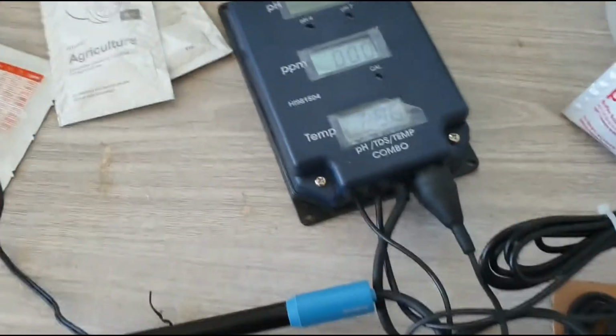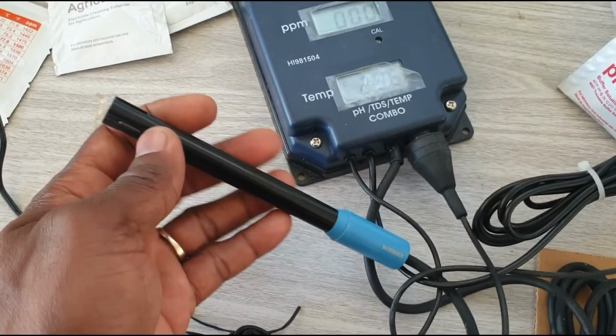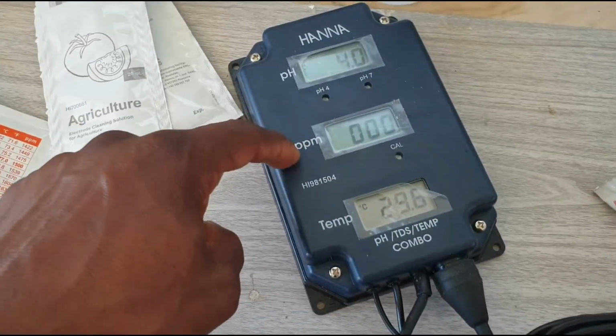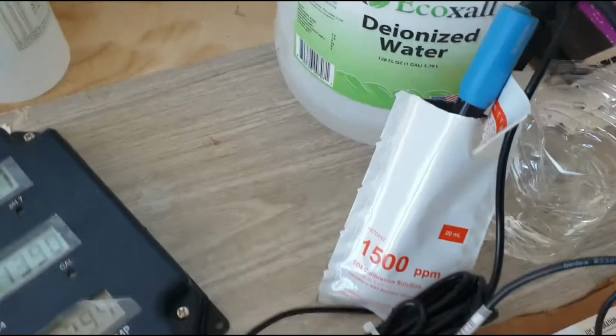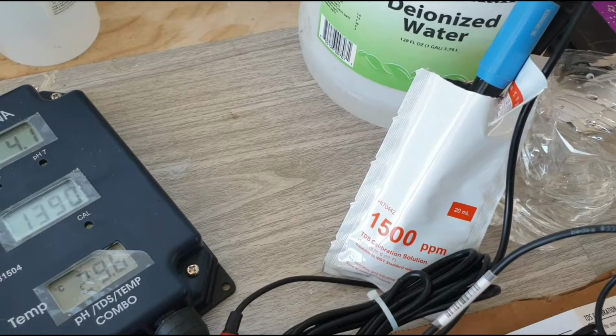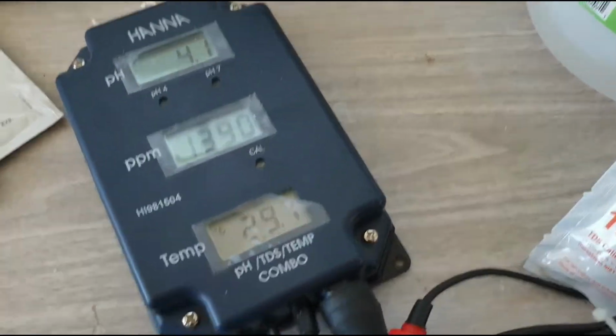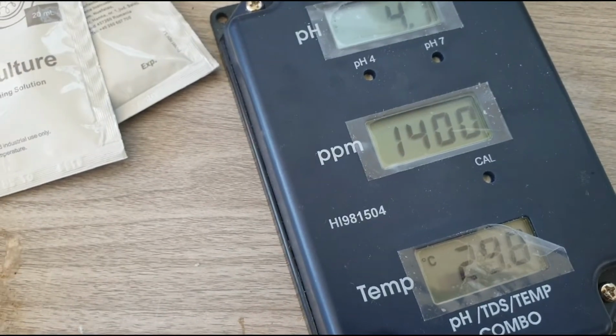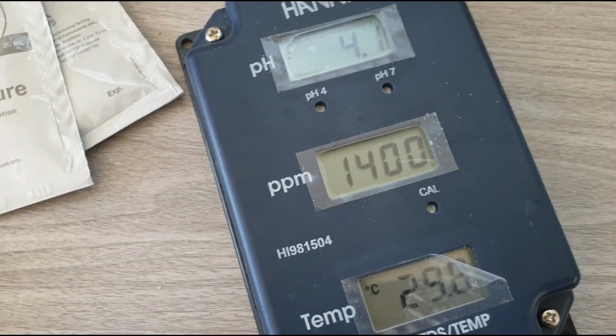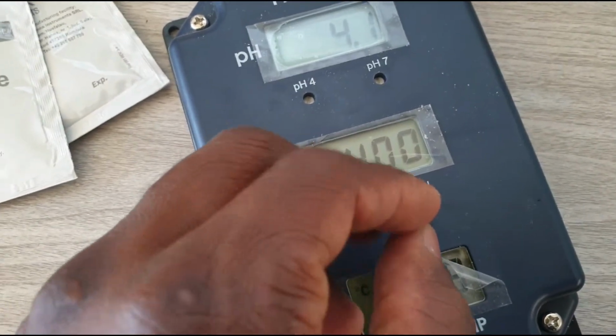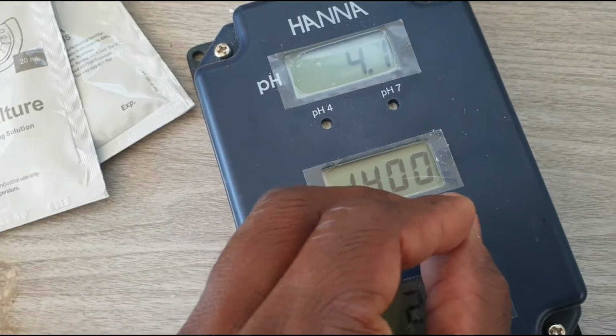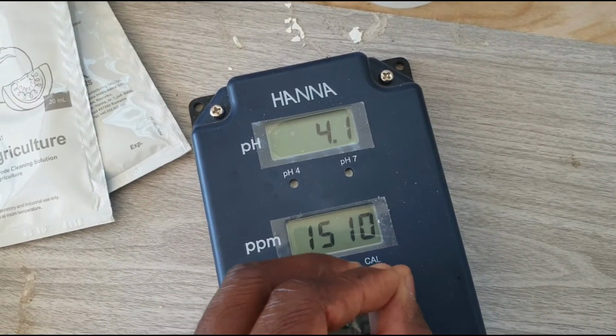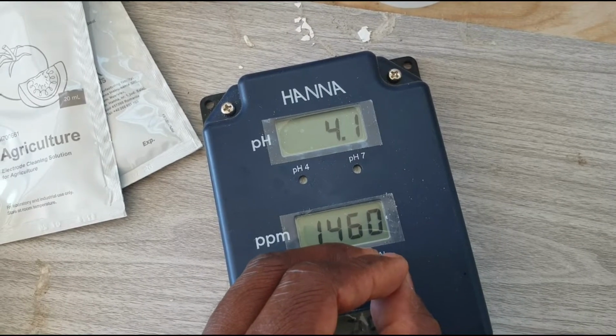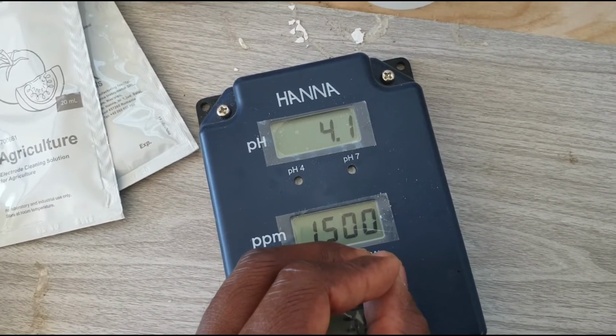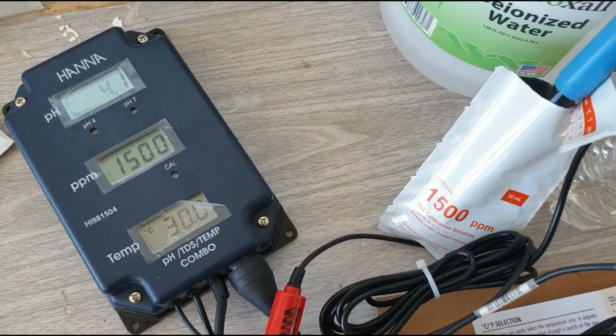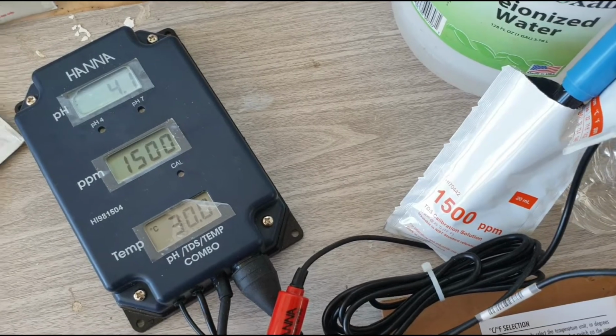So we are going to the TDS now. We are going to calibrate this probe or the machine in ppm value, and remember we're shooting for a value of 1500. So here we are. The probe is in the 1500 ppm calibration solution. As you can see, we are measuring 1390, 1400 ppm. So what we're going to do is go to this knob here, which CAL stands for calibration, and turn the knob until it reaches 1500. Just give it slight turns at a time. So the machine is successfully calibrated for both ppm and pH, and it is ready for use.